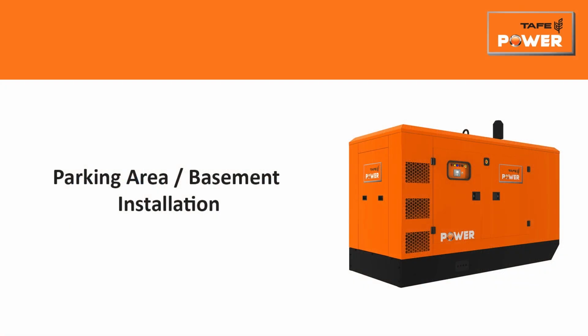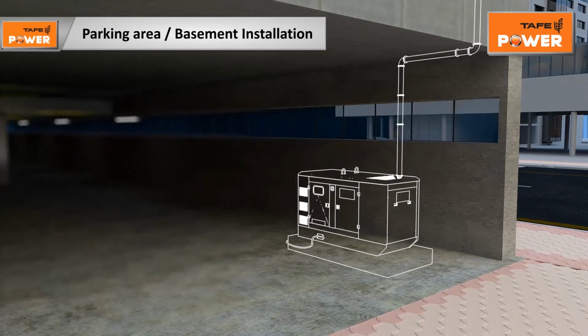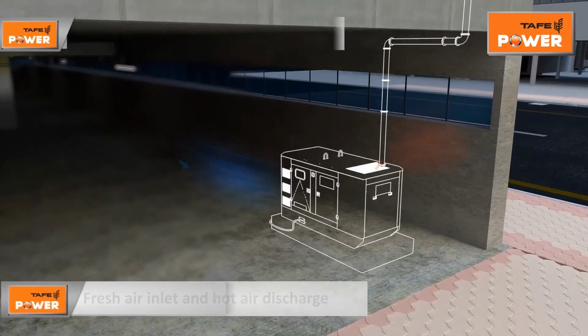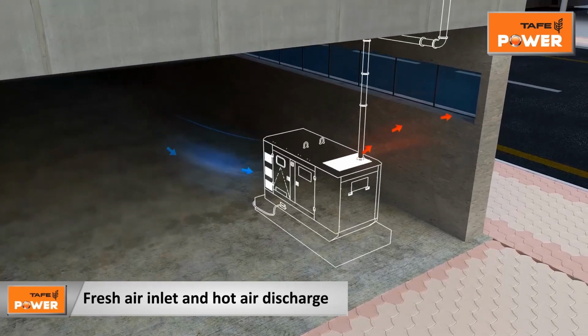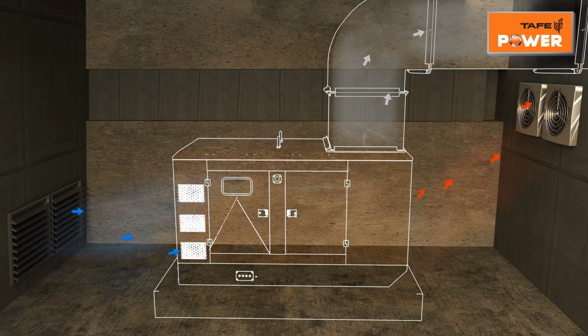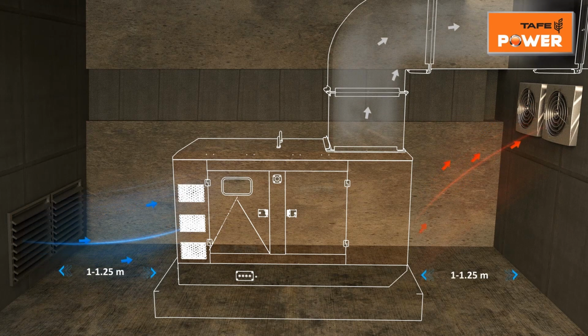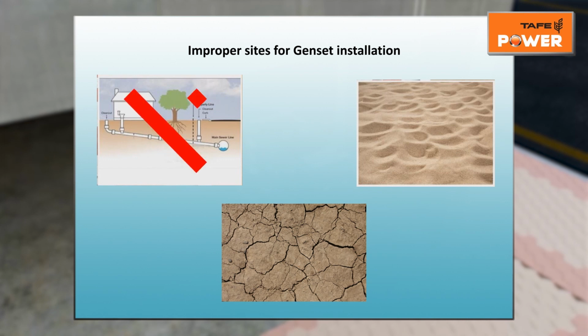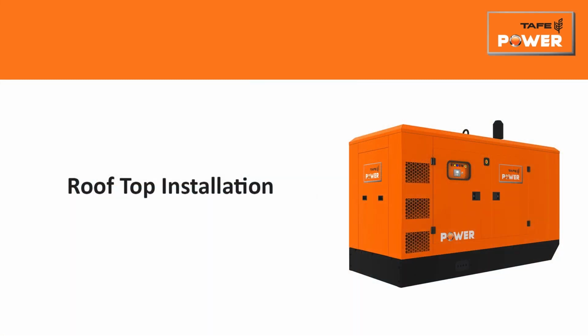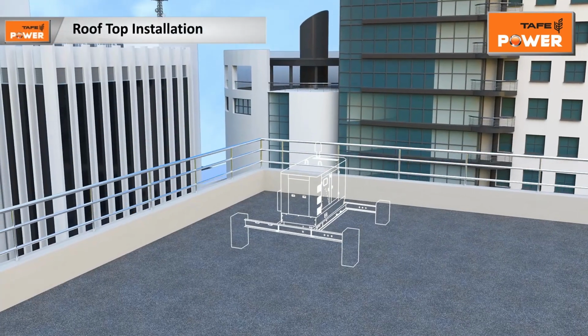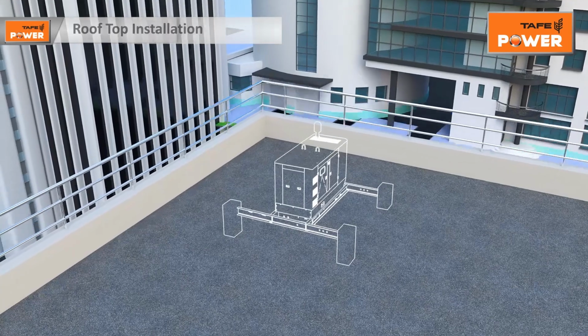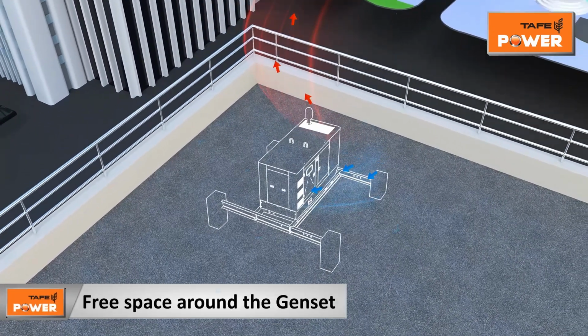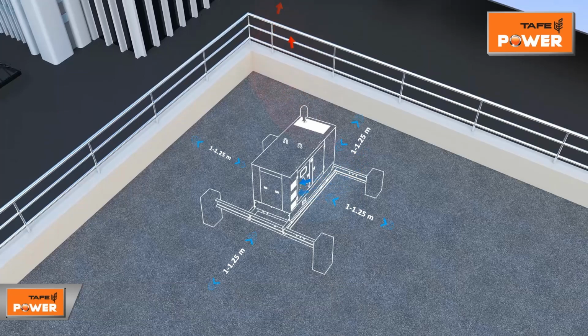Parking area, basement installation. For parking area or basement installation, maintain cross ventilation for fresh air inlet and hot air discharge through proper opening. For installation in closed area, ensure proper ventilation through use of ducting and installation of sucker and blower fans. Ensure free space around and above the genset for free flow of air. Genset foundation should not be made over any basement, water tank, sewer line, loose sand or clay. Rooftop installation. For rooftop installation, protection boundary wall needs to be ensured for safety of operator. Free space of minimum 1 to 1.25 meters should be maintained around the genset.